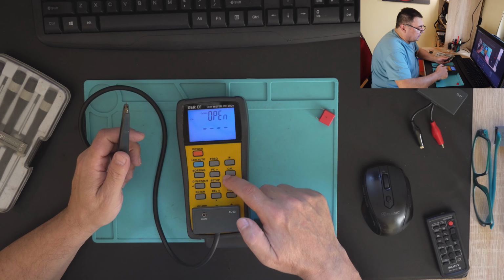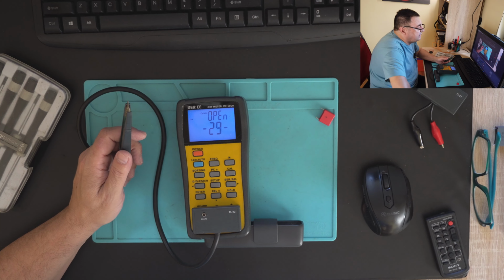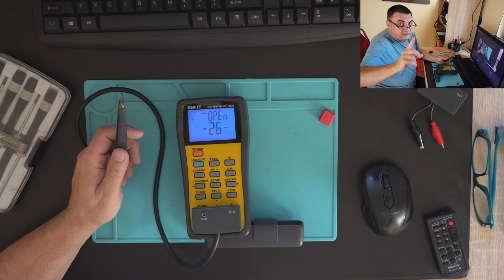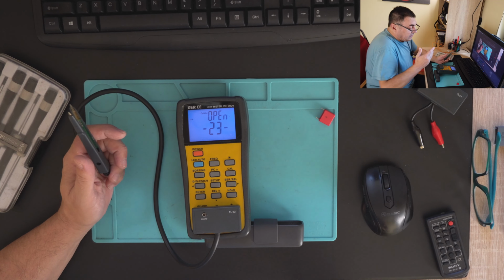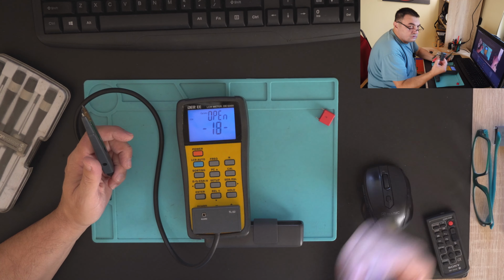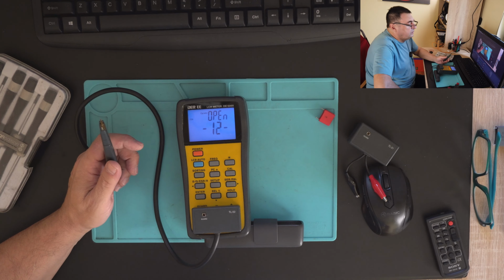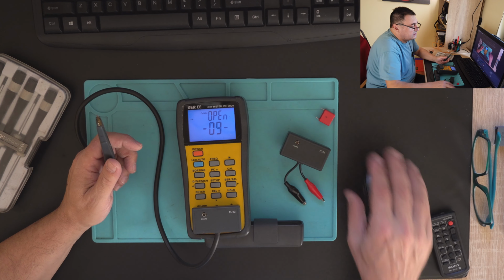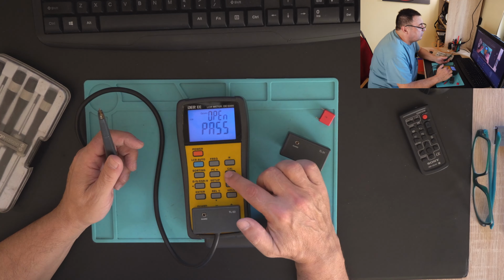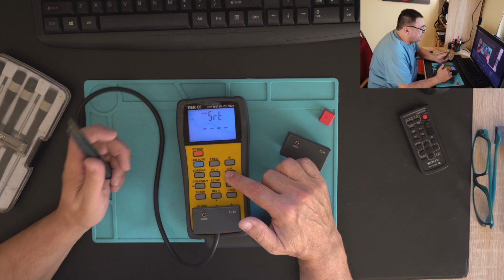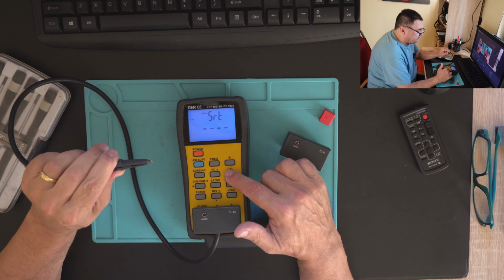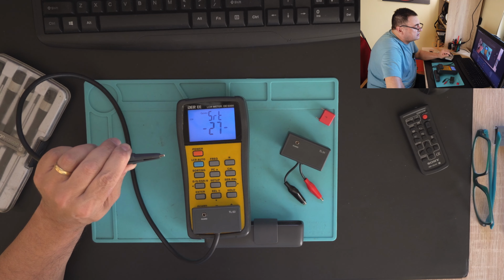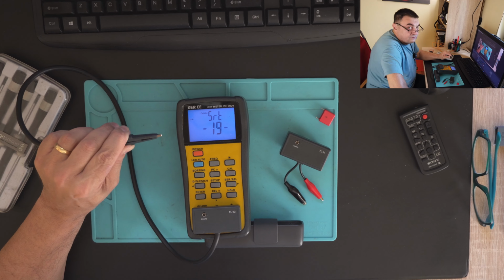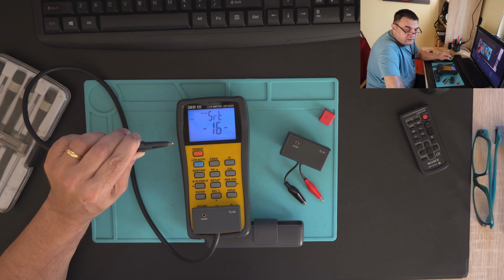So let me try to do a calibration with this guy. Once again, and it starts counting. We have to wait for half a minute. You see, this is the single problem I see. You have to calibrate the probes. If you are using this one, TL21 instead of TL22, as soon as you are changing the devices, you should have a new calibration. Open pass. And now the short one, we have to keep the tips closed for 30 seconds. Remember, it was 94 something, 94 nanofarads, 94.7, I recall. You have to be patient if you want to have good results.